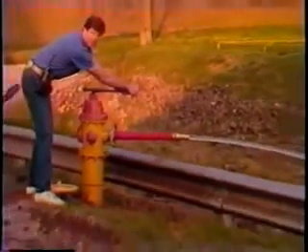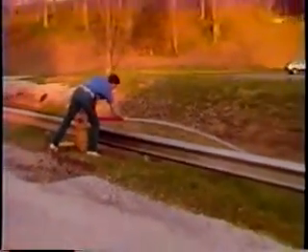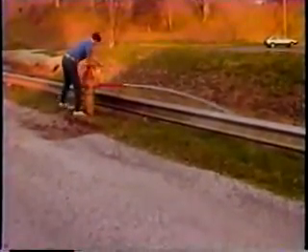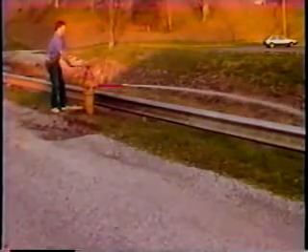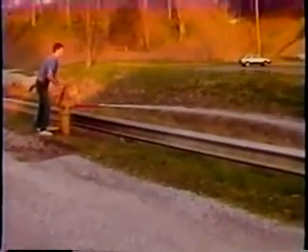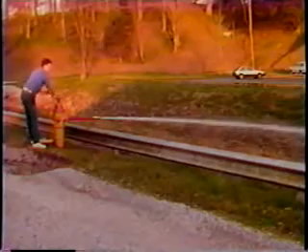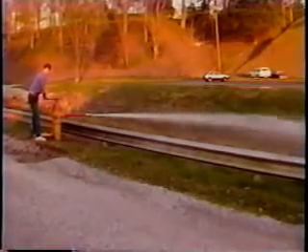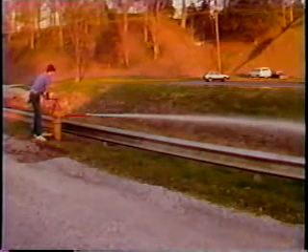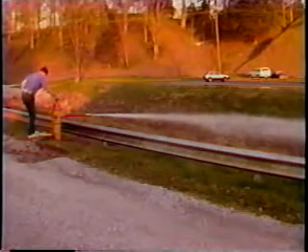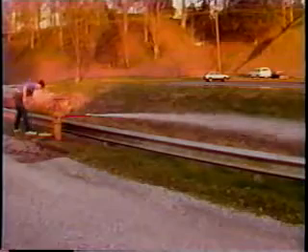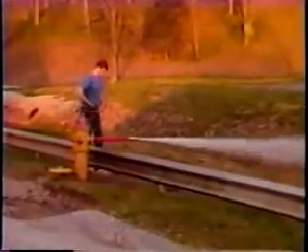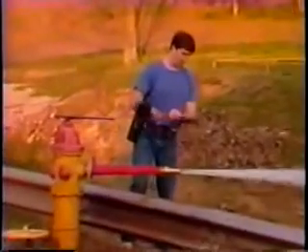For wet barrel hydrants, or hydrants for which you don't know the discharge coefficient, it's possible to attach some type of pipe to the outlet to smooth out the flow. In particular, an underwriter's play pipe, which you see here, is a good way to have a known discharge coefficient. It happens to be 0.97. The problem in using an underwriter's play pipe, though, is that you don't use the diameter of the hydrant outlet, but rather the diameter of the tip of the play pipe as d in the equation we just showed you.